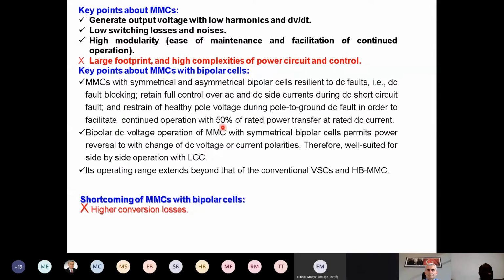And unlike the conventional VSC or unlike the half bridge, here you have a new degree of freedom because, as I mentioned earlier, in VSC you can reverse the power by change of the current polarity. While here, if you have bipolar, you have the capacity to reverse the power flow either by change of the current polarity or DC voltage polarity. I will show this one later. And also its operating range extends beyond that of conventional VSC and half bridge MMC. As I mentioned, you can operate with positive DC voltage or negative DC voltage.